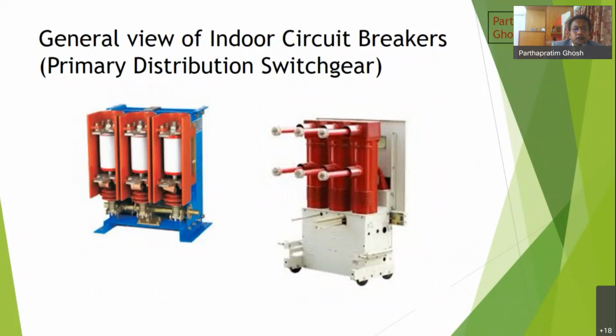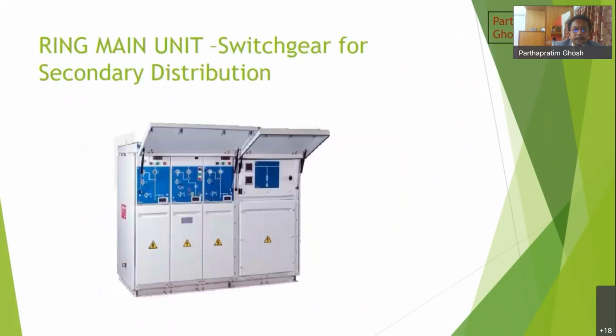This is the circuit breaker portion of the indoor circuit switchgear. This is a specialized switchgear for secondary switchgear application. This is RMU. There are various combinations. In outgoing, this is a combination of circuit breaker and isolators. The typical combination is that the middle one becomes a circuit breaker and the outer feeders are isolators.